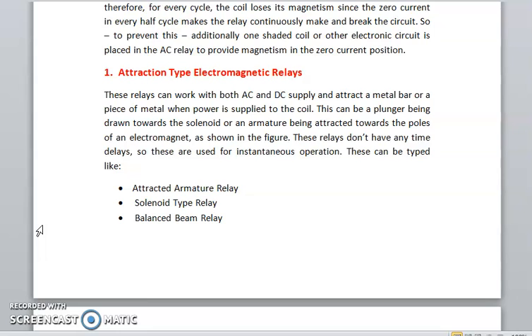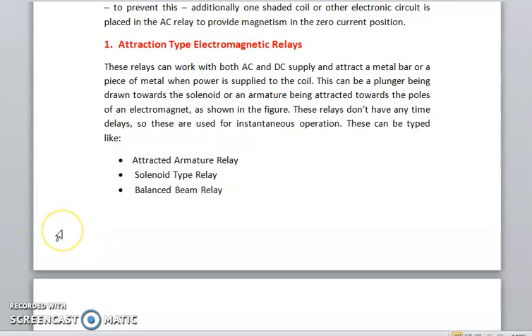The first type is attraction type electromagnetic relays. These relays can work with both AC and DC supply and attract a metal bar or a piece of metal when power is supplied to the coil. This can be a plunger being drawn towards the solenoid or an armature being attracted towards the poles of an electromagnet. As shown in the figure, these relays don't have any time delays, so these are used for instantaneous operation. These can be typed like attracted armature relay, solenoid type relay, and balanced beam relay.